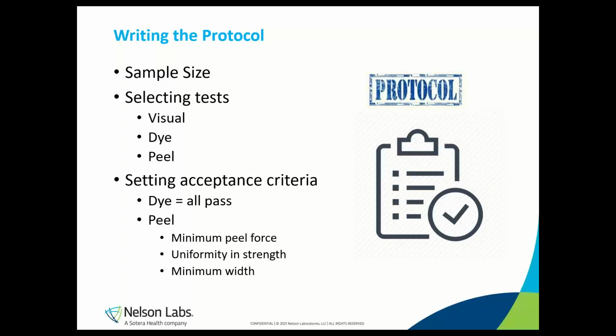A minimum seal width specification should also be included in the protocol. EN 868-5 says that seals shall not be less than 6 millimeters, and for rib seals, the sum of the widths of the ribs shall not be less than 6 millimeters. Since seal width is dictated by the sealer, be sure to purchase one that makes seals at least 6 millimeters wide, but depending on your device, you may need an even wider seal.